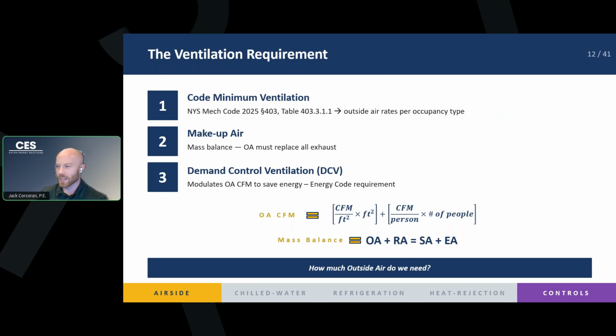And then lastly, demand control ventilation. I'm just going to touch on it. It is a much deeper topic, but essentially the first two are fixed values, right? You're going to end up with a solid number. But energy code requires demand control ventilation for certain occupancy types. And essentially all it is, it allows you to modulate the amount of outside air you bring into the building.